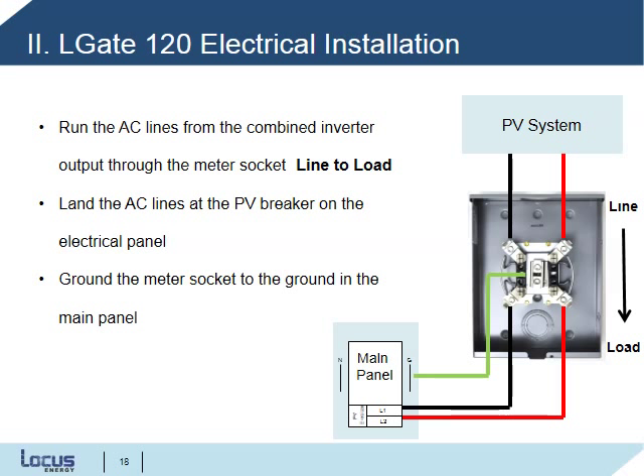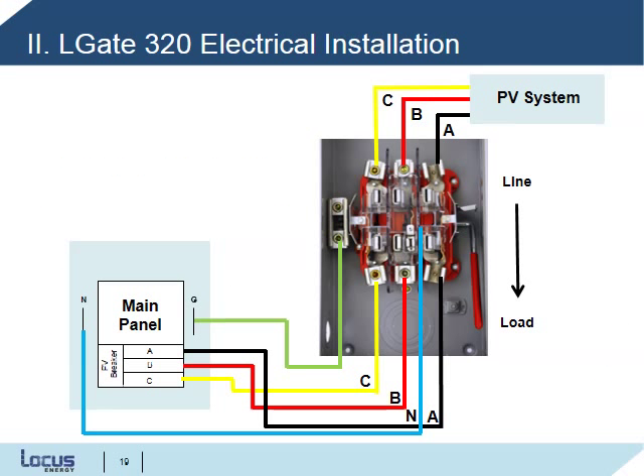After mounting the meter base, run the AC lines from the combined inverter output through the meter socket, line to load. Land the AC lines at the PV breaker on the electrical panel and ground the meter socket to ground in the main panel. Now for the LGate 320, we'll be running the AC lines combined inverter output through the meter socket, line to load, so that's top to bottom. Ensure that you run neutral and land ground to ground at the main panel.